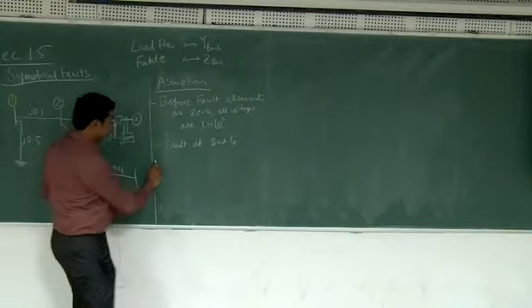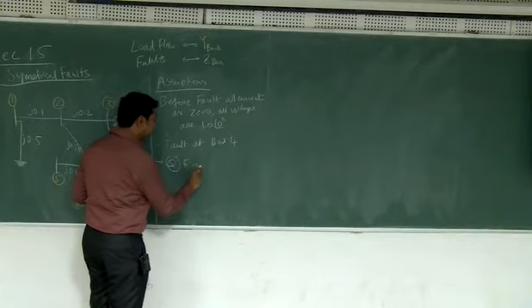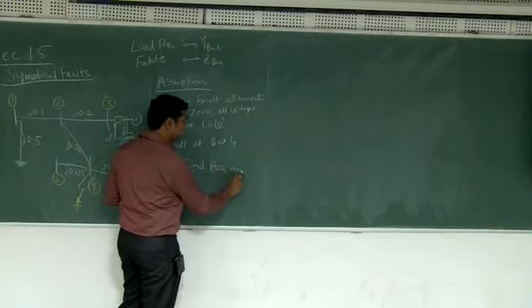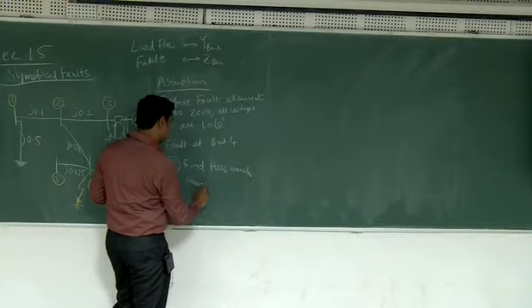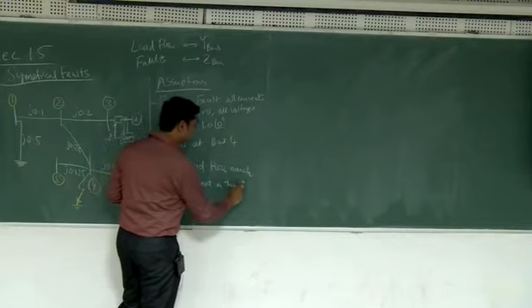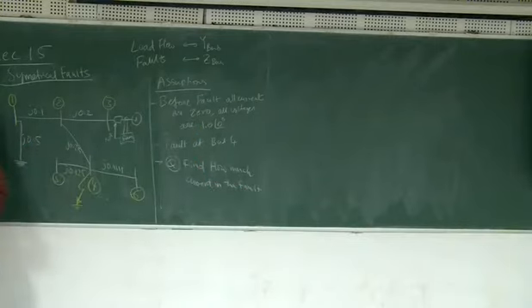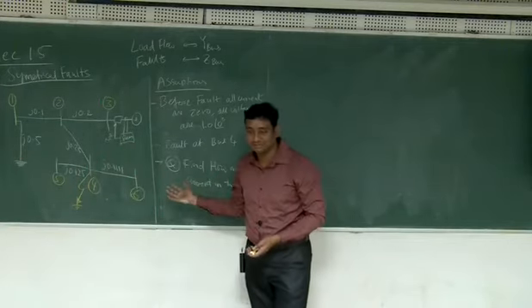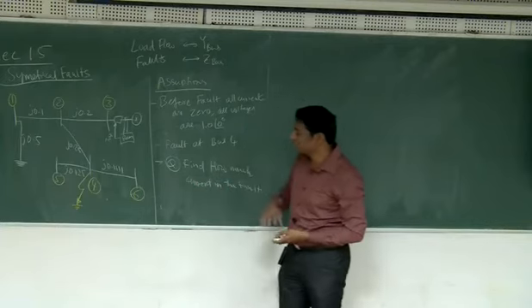So the question is, find how much current is flowing in the fault. So how much current is flowing in that fault if there is a fault? And the use for that is that if I want to put a circuit breaker there, I should know how much current it has to withstand to break it. So for the designing of the circuit breaker. So without using the bus matrix, if I give you this problem, how will you solve? Actually, you can right away go ahead and solve it also.